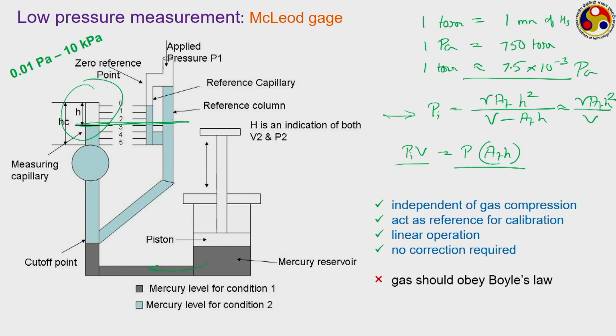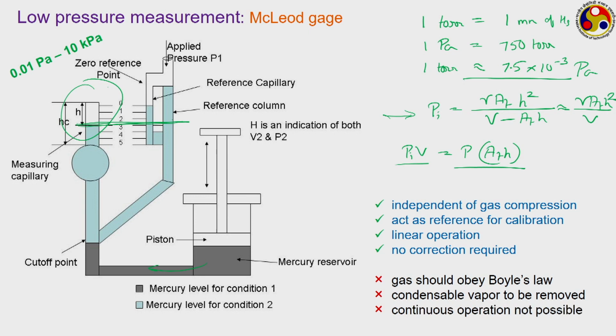We get a straightforward relationship between P and H, with no correction required, and whatever we get from this relation is the final pressure we are looking for. However, the gas must obey Boyle's law, since that is the founding principle. If condensable vapor is mixed with the gas, it can significantly affect the measurement, so a corresponding correction must be applied. Continuous operation is also not possible, since we have to bring the system back to its initial position before starting another reading.